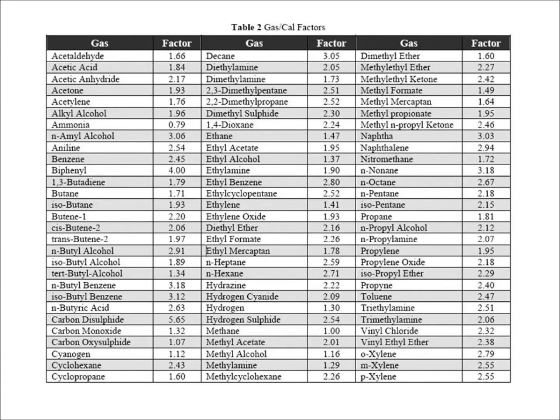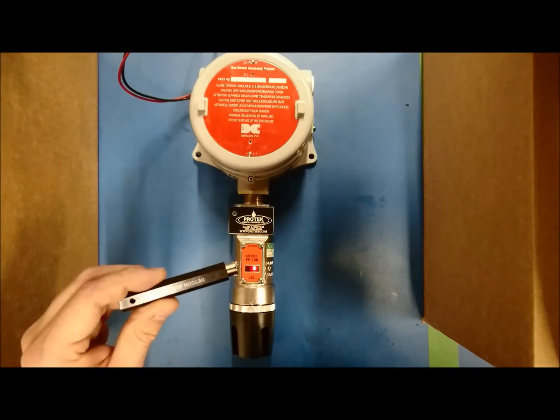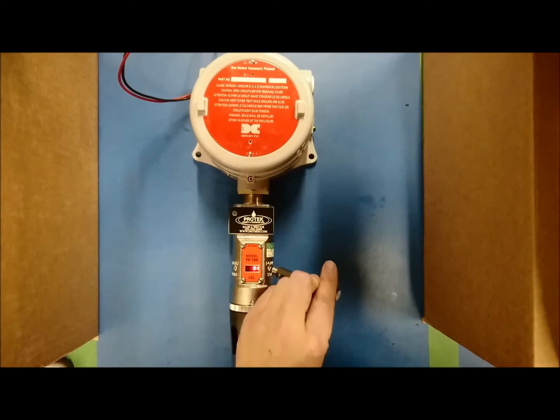If you need guidance with how to determine what the gas or calibration factor should be set at, please refer to the manual that came with the unit. With the unit powered up, hold the Detcon programming magnet over PGM2 for 5 seconds.